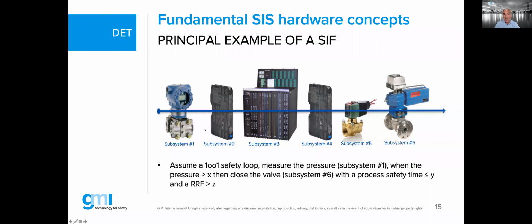And you can already imagine how many different subsystems and different configurations you could potentially have in here. But the final element at the end is to de-energize. You take away the instrument air to go to a safe state. And of course, if you have a safety instrumented function description, we need to know what we have to measure, what we have to do in terms of logic in the middle, and what the final element is. Basically, if you talk about safety instrumented systems, or a de-energized to trip application, we always go over a digital output from our control platform into a final element environment. So we open or close a valve, we start or stop a motor. Those are about 95% of all the potential safety instrumented functions out there in the market.